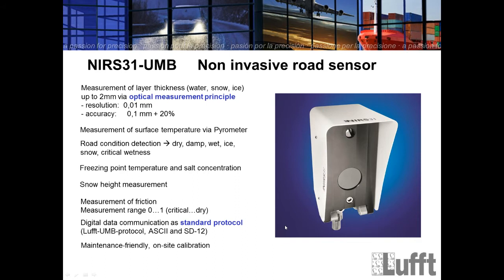The second option, which you configure with the UMB config tool on the NIRS, is that you get the actual surface temperature instead, for example -4 degrees, used as the freezing temperature since this is the minimum possible when ice percentage is 0. I hope that's clear - these are the two options you can choose using the UMB config tool.